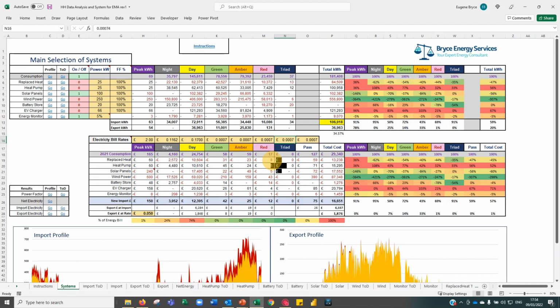Finally, the triad charges, which could be about £45, but only for a very small percentage of time. You can see here there's only a very small number, but it's multiplied by a big value. In this example, if we did apply triad charges for this customer, if I put, let's say, £45 in, you can see that the triad costs £1,600. That is included in the fixed contract rate for this particular customer. But for most half-hourly, you're on a pass-through contract and triad charges would apply.